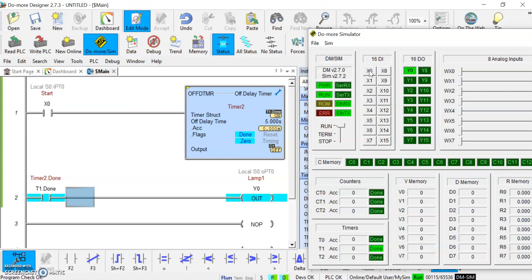And you can take advantage of using both of them. They both have their own unique set of circumstances that you would use an off delay timer and an on delay timer. Sometimes you need one motor to run for a period longer than one motor when you shut one motor off. One motor might be a feed motor and the other might be a conveyor. So once you stop feeding onto the conveyor, you need the conveyor to run for another 20 seconds to get the product off of it before you would want to restart it. So there's different scenarios where you would use different timing functions. So that's just a little bit that I wanted to show you there. With the on delay and off delay timers.